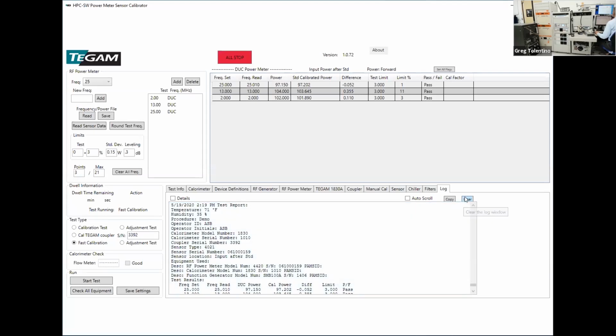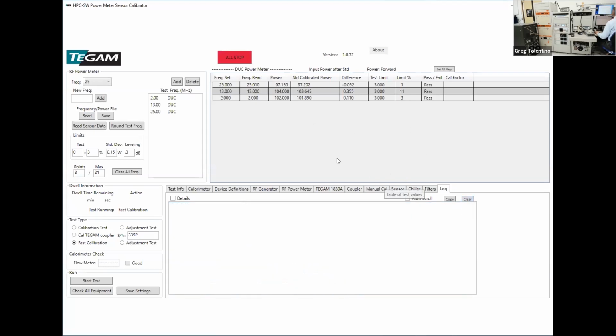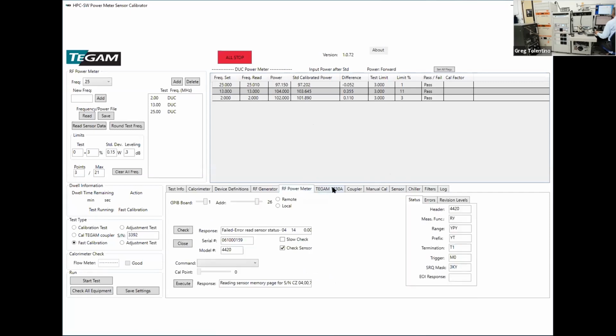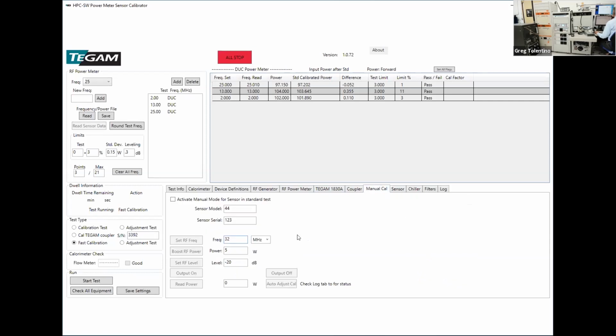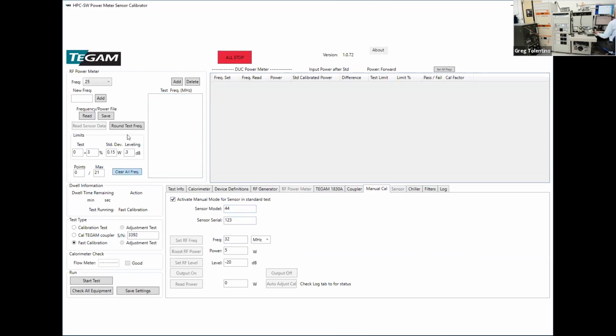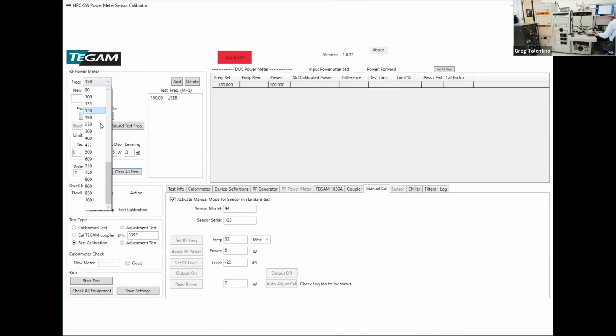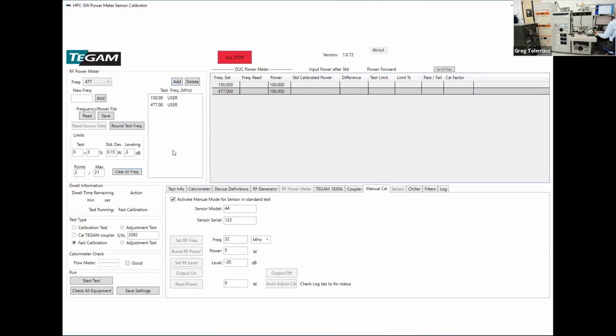So there's a couple of very minor setup changes we have to make. We need to go to the RF power meter, and we need to close our connection with it. Then we need to go to the manual cal tab and say, let's do this in manual mode. And then we need to pick some appropriate frequencies to test that meter at. 2 megahertz is not one of those. I think we should test that meter at 150 megahertz, and I think we should test that meter at 477 megahertz. And more than that would just get redundant.